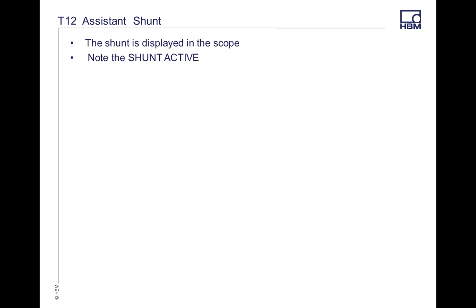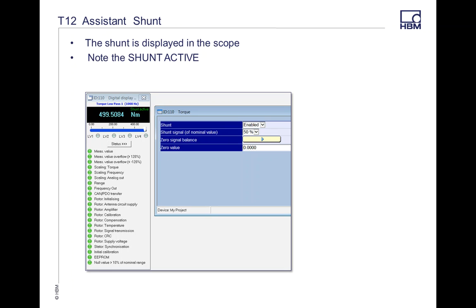When that is active, you're going to turn your shunt to active, enabled at 50%, and your value is going to be here. In this example, I have a 1,000 Newton meter torque transducer, so it's running 499.5. So that's it, the shunt is active.